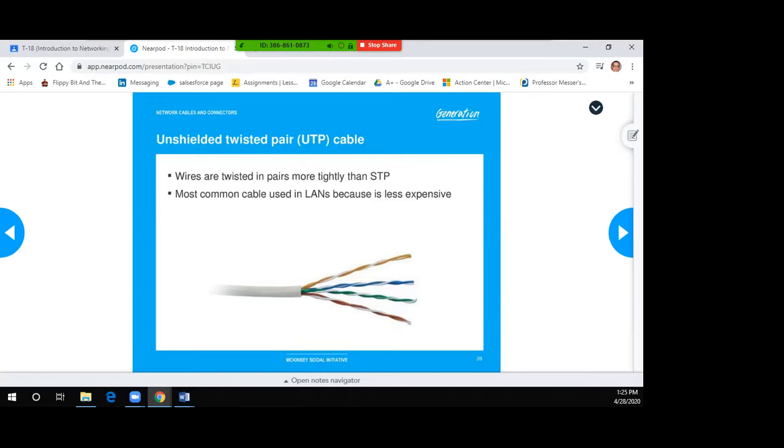The previous one is mostly used when you're running it on top of lights or near lights, those fluorescent lights in facilities, since they create so much electromagnetic interference, or EMI. Basically, that's why you would buy the more expensive one. So the ones that are usually going in the wall and that don't have that many problems, you would just use this one. Any questions?